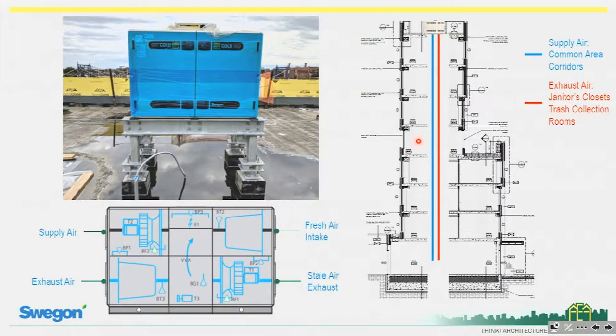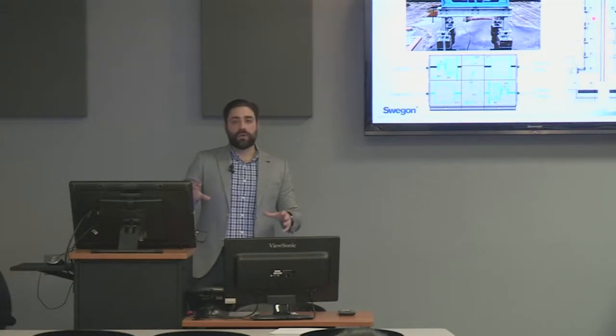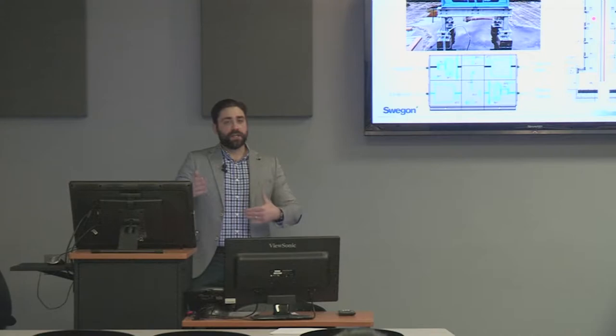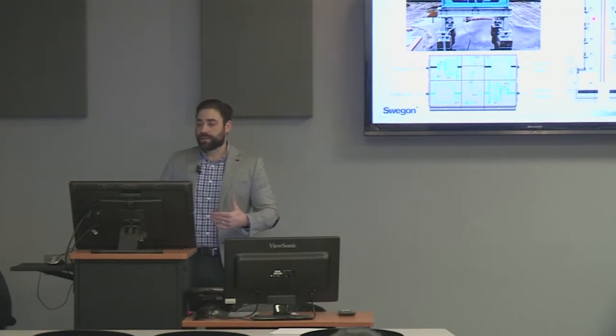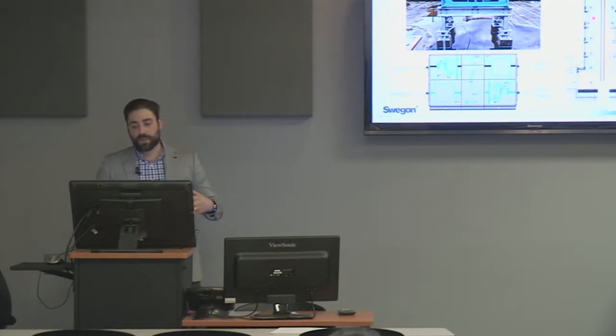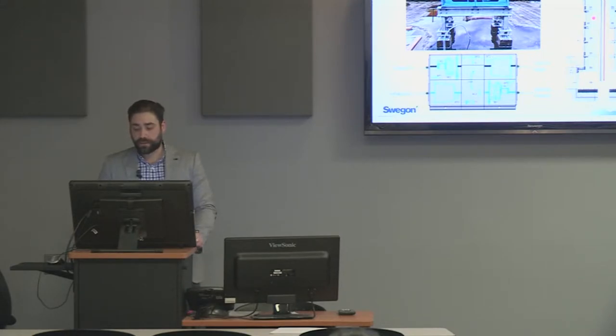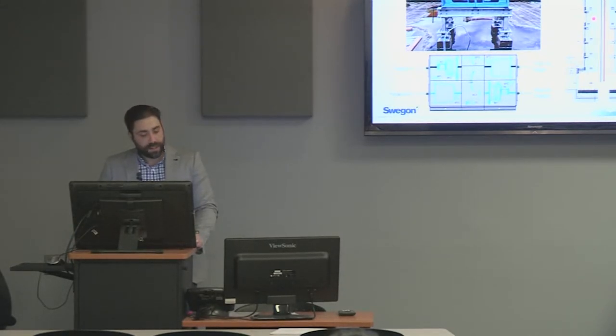There are actually two ducts running down through the building. We're exhausting out of the janitor's closets and the trash collection rooms, and then supplying fresh air into the common area corridors. So again, we have this balanced ventilation approach, and we're able to ventilate the common area spaces as well as the first floor commercial facility.